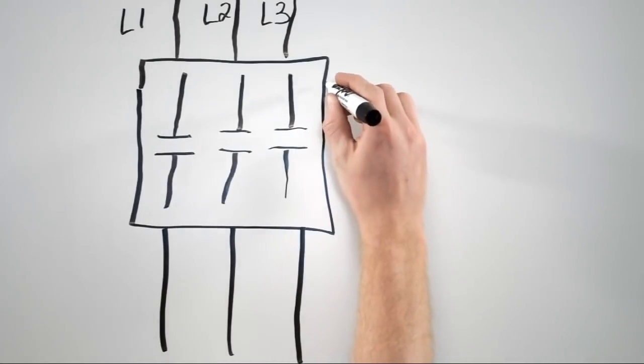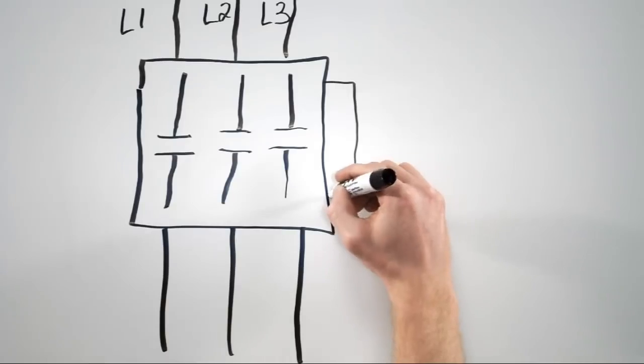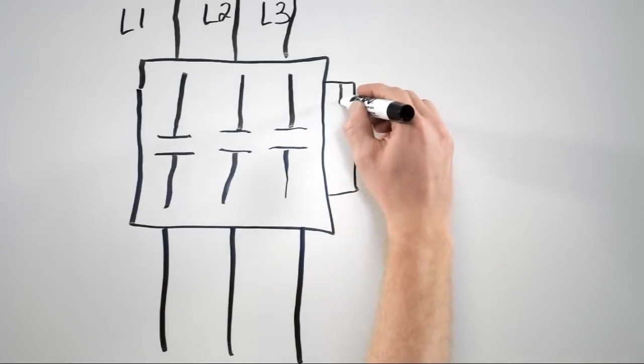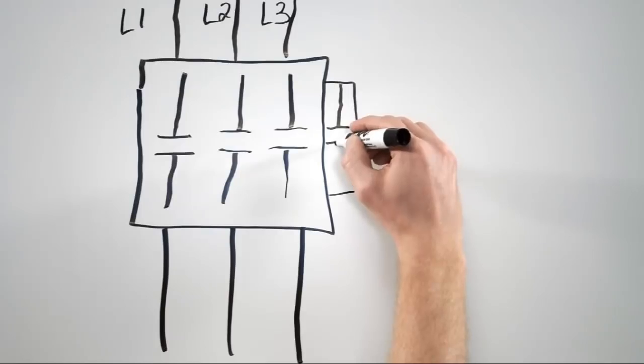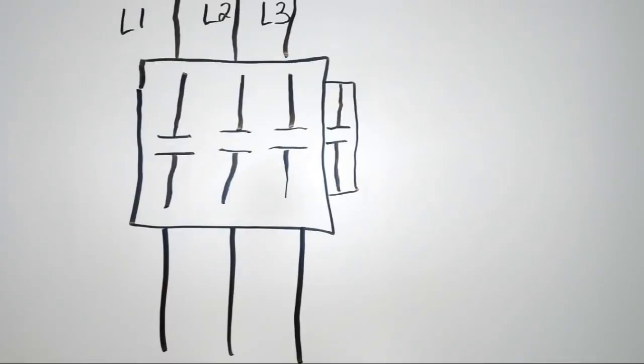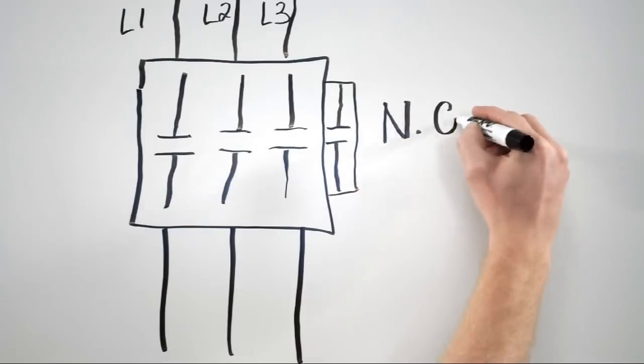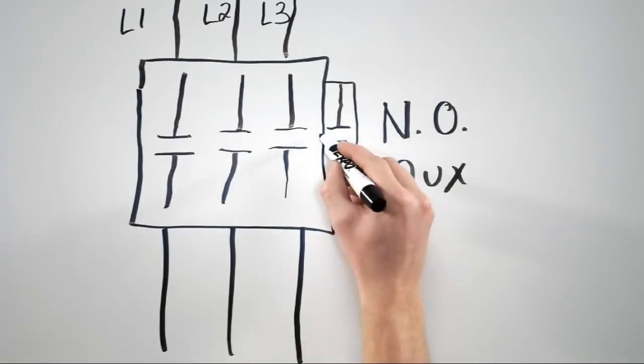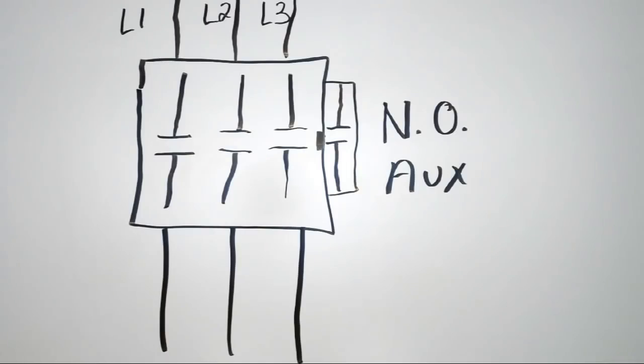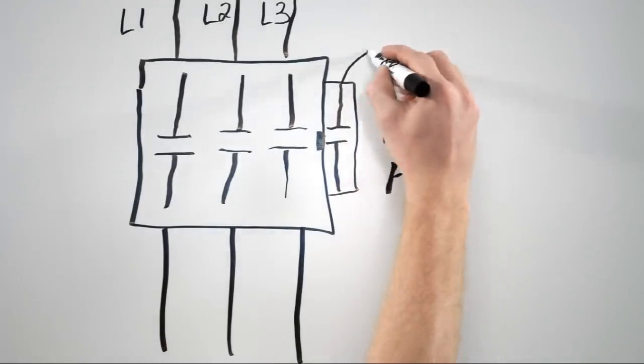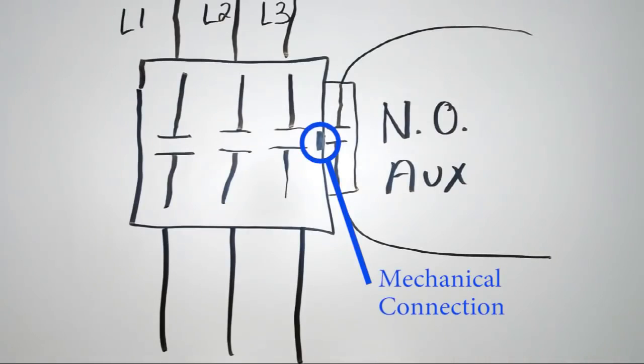Well, there is a very common accessory that gets added to contactors called an auxiliary contact. Often it's mounted to the side of the contactor, and inside the auxiliary contact module, we have an electrical contact that can be normally open or normally closed. If you grab a normally open auxiliary off of the shelf, it will not pass electricity through it unless it gets changed by an outside force. When it gets attached to the side of a contactor, there is a mechanical connection between the auxiliary contact and the moving parts inside the contactor.